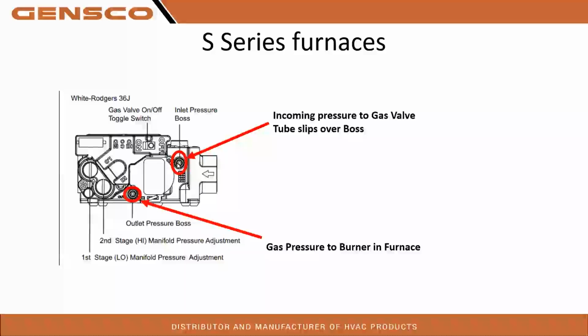We have these inlet pressure bosses, and there's a little Allen screw that goes in here that is secured down. So what you want to do is get your Allen wrench and just loosen it up. You don't have to take it out, just loosen it up. And then you're going to slip your tubing right over the top of that boss. It's like a castle wall, if you will. And that little Allen screw is down there in that boss a little bit. So we have the inlet pressure boss. Then when you take your tubing off, you want to tighten that guy back down.